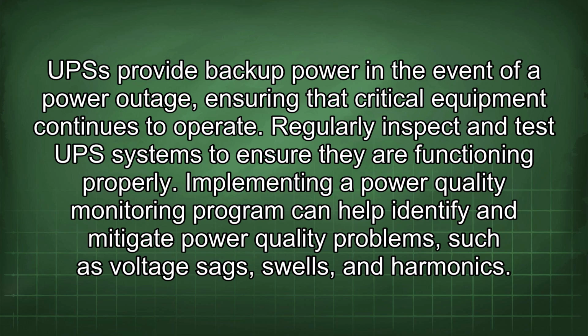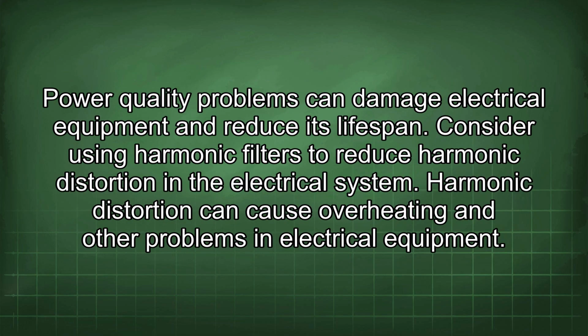Regularly inspect and test UPS systems to ensure they are functioning properly. Implementing a power quality monitoring program can help identify and mitigate power quality problems such as voltage sags, swells, and harmonics. Power quality problems can damage electrical equipment and reduce its lifespan. Consider using harmonic filters to reduce harmonic distortion in the electrical system. Harmonic distortion can cause overheating and other problems in electrical equipment.